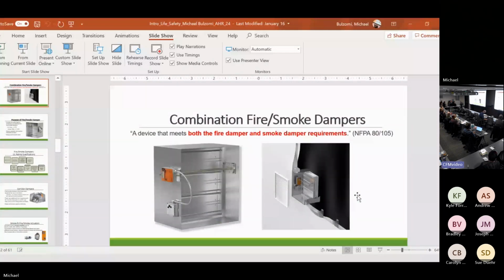This is what we call an out of wall fire smoke damper. The damper normally is tested with the blades in the closed position within the plane of the wall. So I have an opening in the wall, and the damper closed is somewhere in that wall. Picture a red dotted line down the center line of the damper, it's in the wall. Well, I'm in a shaft, or maybe I'm in the corridor of residences and I cannot get access to the residences behind it. Maybe there's an obstruction. I could do my service through the face of a grill. I test the damper to where the damper is outside of the partition a specified distance. So for Greenheck, wood stud, 7.5 inches, steel stud, 8.5 inches.